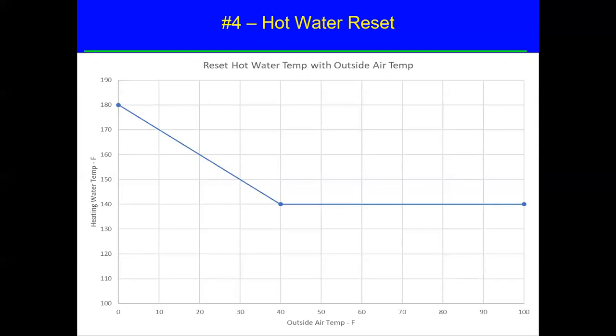So sometimes you need hot water for reheat purposes. Sometimes for dehumidification, you will cool the air colder than it needs to just to maintain the space in order to wring the moisture out, and then you have to heat it back up again. So even in the summer months, for some types of systems, we need what we call reheat water. You might just keep that set on 140, you might take it down to 120, something like that. It's up to the engineer. But that's what a reset schedule, or a curve, looks like for resetting hot water heating temperature with outside air.